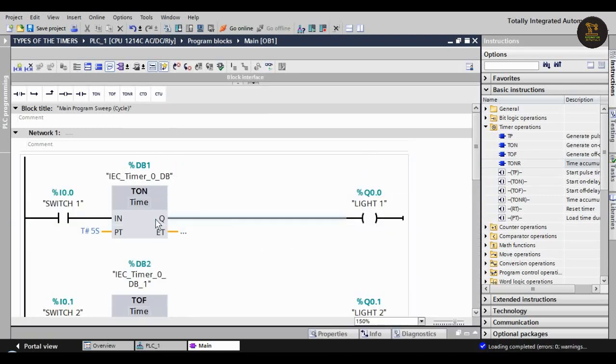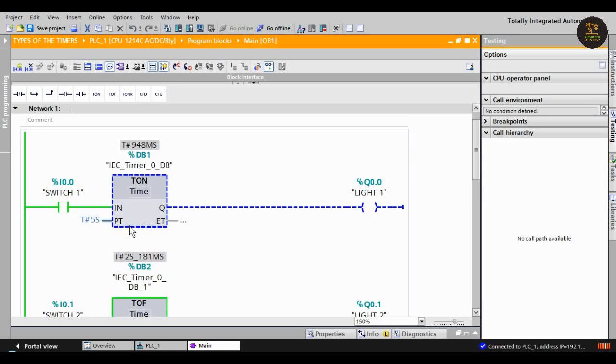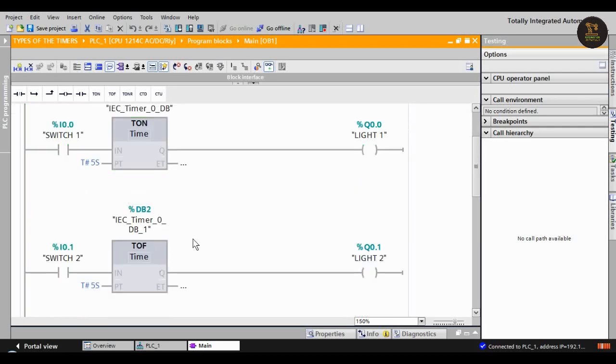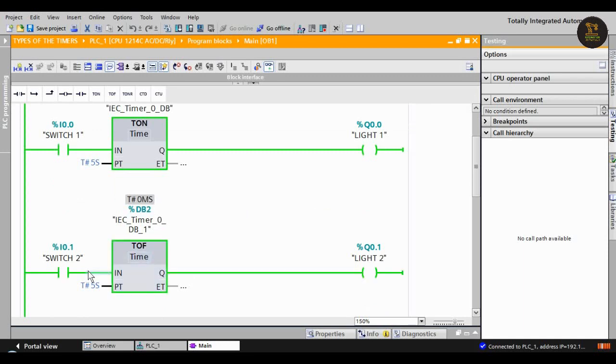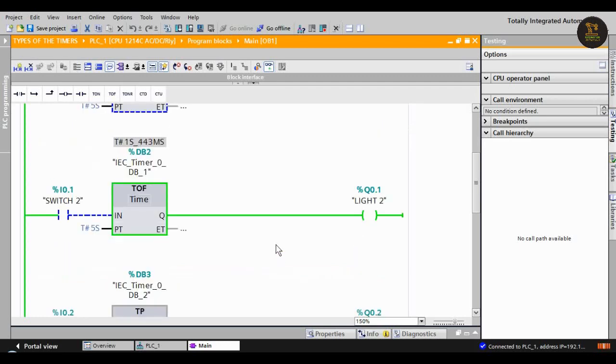Okay, to check this there is a specs icon - click on it for monitoring on or off. Now let's see T_ON. When we press I0.0, after five seconds L1 is on. This is the T_ON timer. Let's see T_OFF - when we switch on, light two is on. When we switch it off, it will turn off after five seconds.